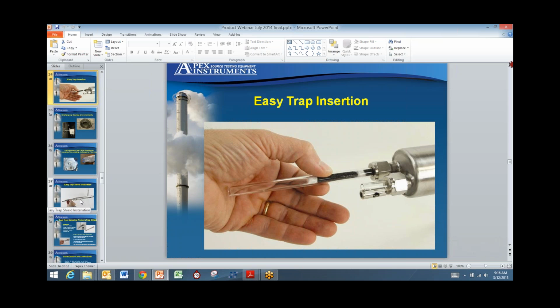The trap design is laid out in the EPA specs, so pretty much any trap that's used to monitor mercury is going to be the same as any other trap in design. You will get variations depending on what you're doing. A 30B trap, like a RATA trap, will only be a 2-bed trap. A PS12B will be a 3-bed trap. You might do longer traps for high acid or different things like that. You might have a scrubber section, but the basic anatomy of the trap is set out in the specifications, and it's pretty standard. Okay, thank you. No problem.